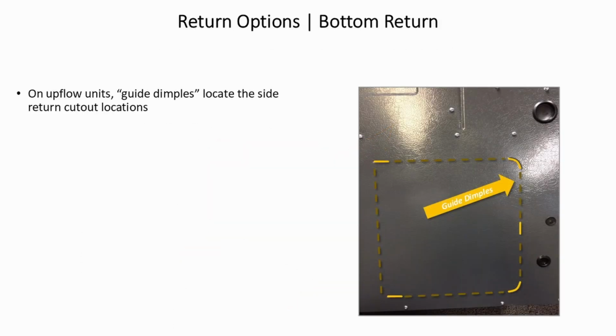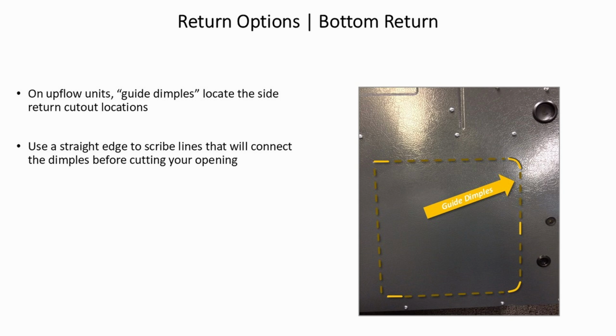On upflow units, guide dimples made at the factory locate the side return cutout locations. Use a straight edge to scribe lines that will connect the dimples before you cut your opening. An undersized opening can reduce airflow.